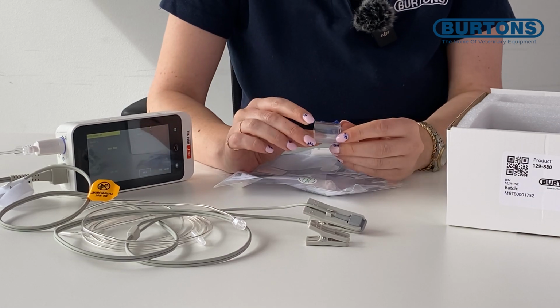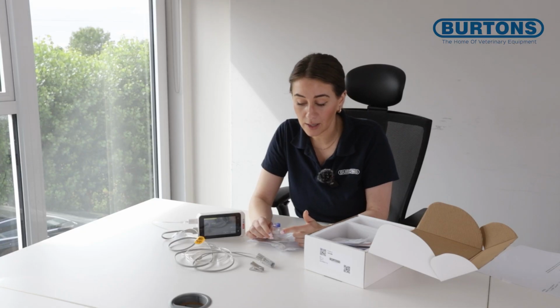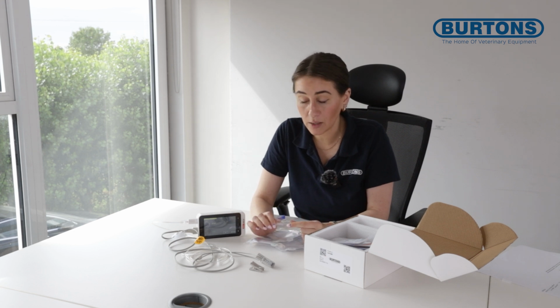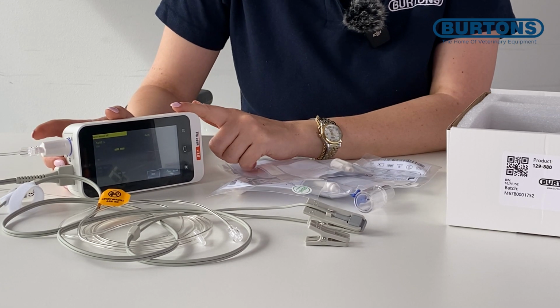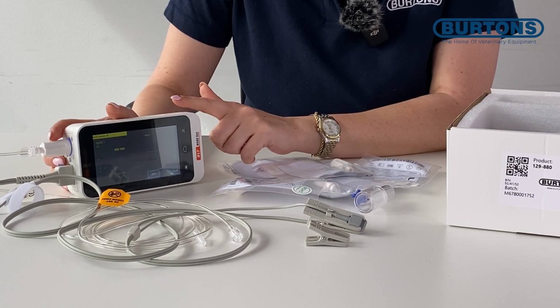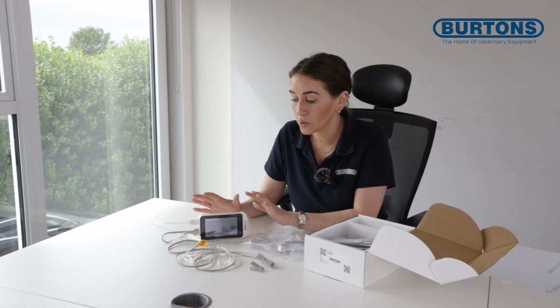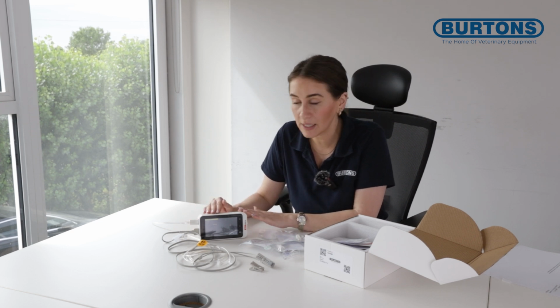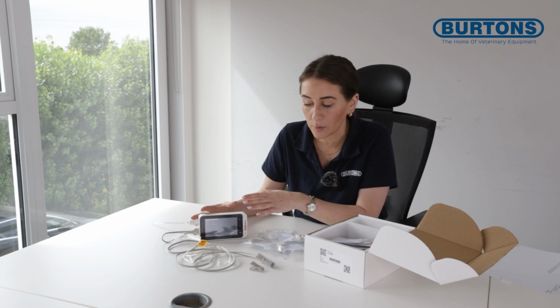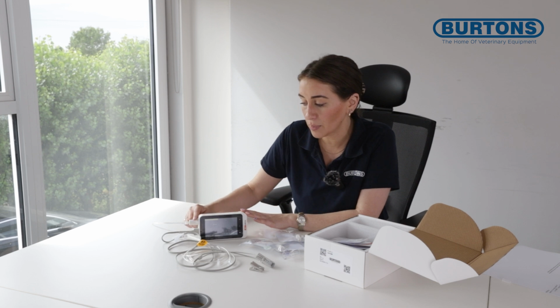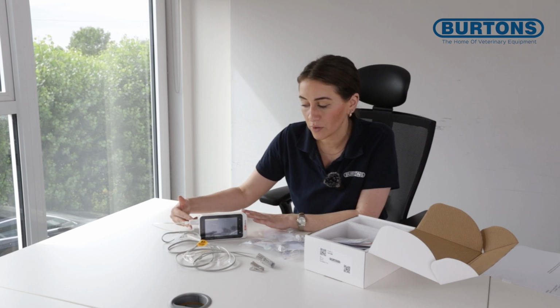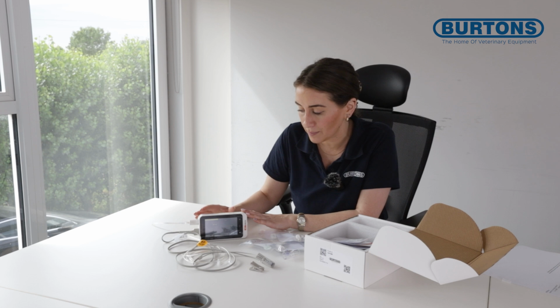The other item included is your airway adapter. These typically can be used and cleaned with your ET tubes and cleaned with the same process that you use for those. The device has an IPX1 rating, which means it's protected against condensation and water droplets. So we really want to minimize the use of lots and lots of fluid on the machine. So it can be cleaned with a hospital grade detergent, used at the lowest concentration and used with like a damp cloth rather than excessive use of liquid, and that's for the device itself, and we want to unplug the two probes and make sure that we keep the ports free of any fluid.